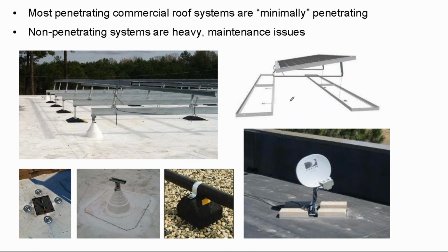But the problem with, I'd say, most of the notable commercial solar fires has actually been the conduit itself. So maybe this conduit idea is not the best. Conduit's made of metal, and the rooftop is hot. And so what happens, particularly if you anchor the conduit support to the roof, or you over clamp, this is supposed to be a secure but loose connection.